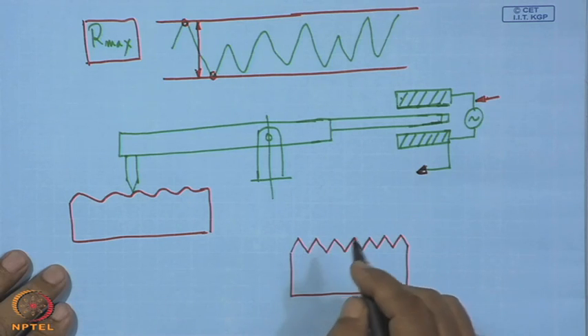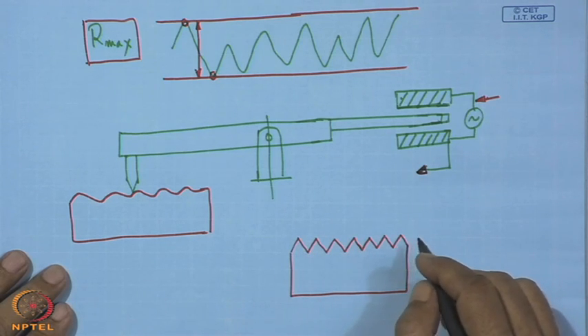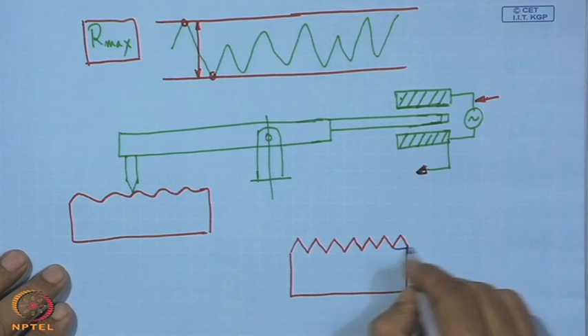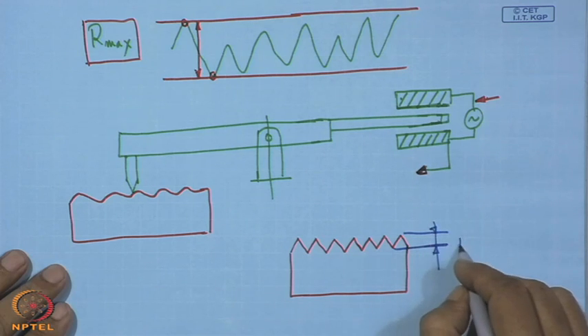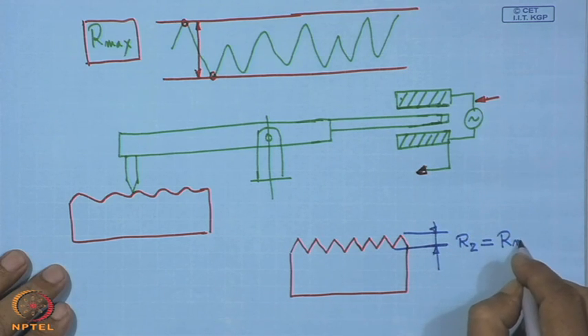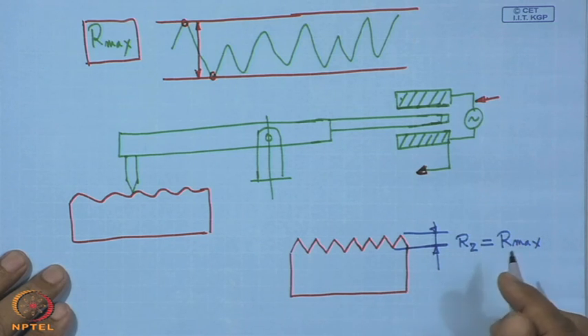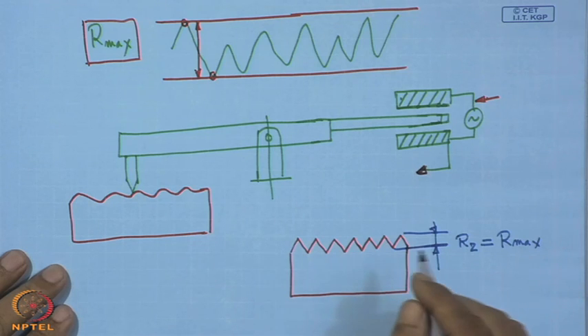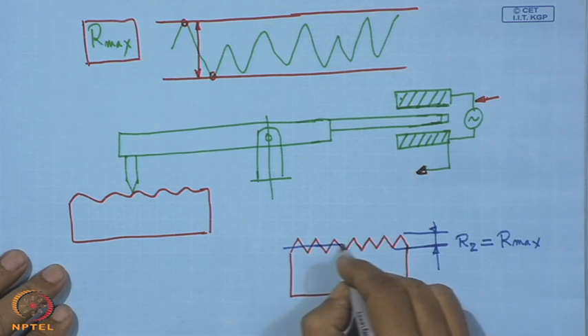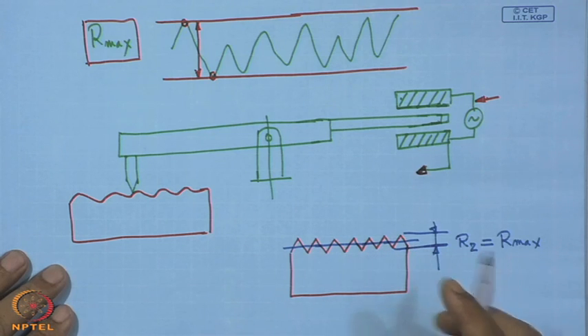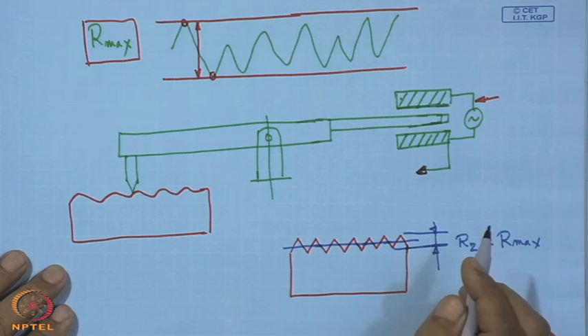One important issue is calibration of this instrument, and for that we have a masterpiece, which is exactly a triangular profile, precisely made with the highest possible precision. Over that, what we see is peak to valley, that is R z, which is actually R max, because all the triangles are of identical geometry. So R z equals R max, and at the same time we can have a center line. Locating the center line is not difficult because it is symmetrical, so it will just go through the midsection.